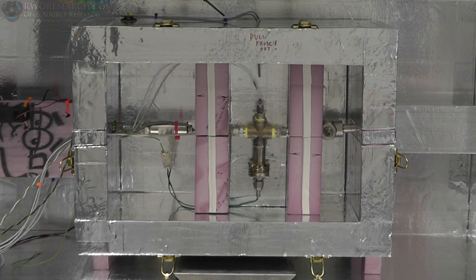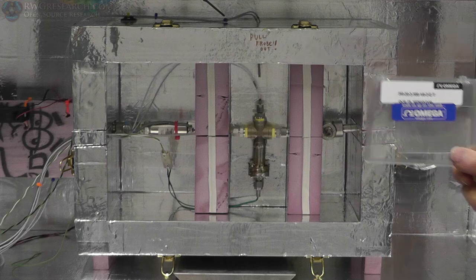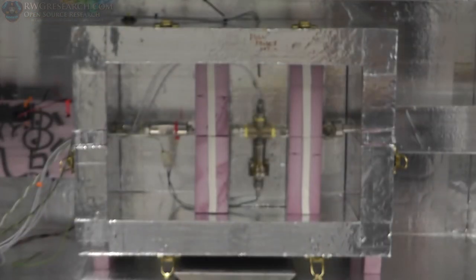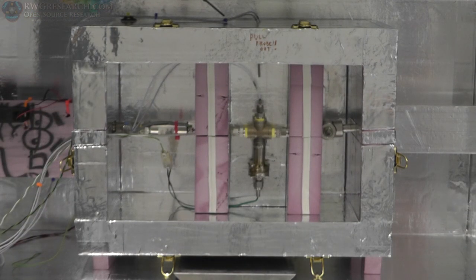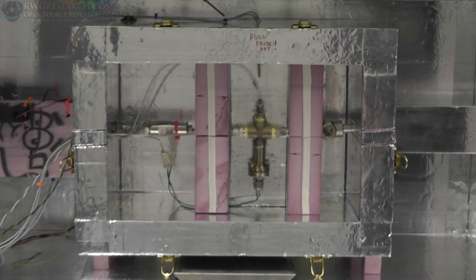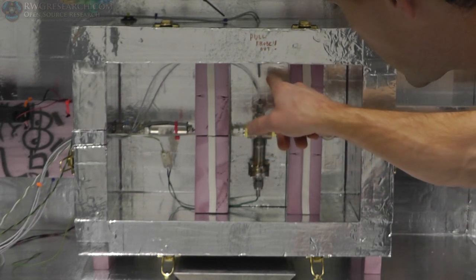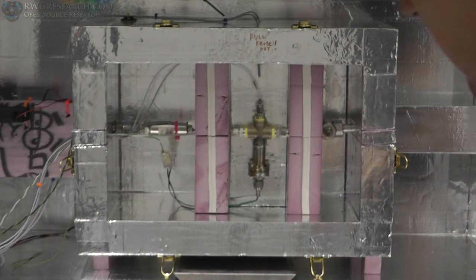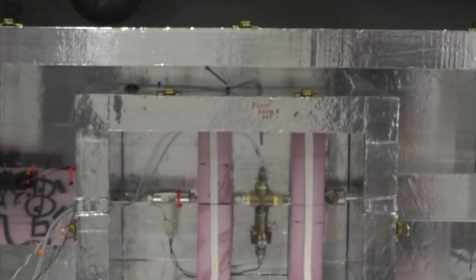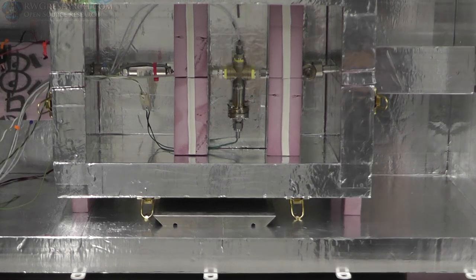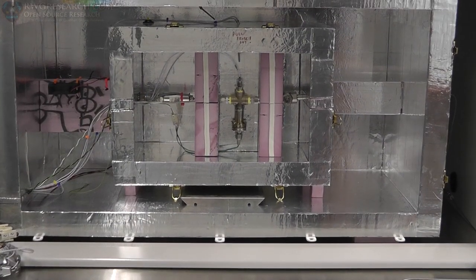Now, I've chosen four-wire RTDs because they are the most accurate that you can get. Here is the omega part number of the ones that I am using. I really like these. The four-wire allows to cancel all resistance in the wire, and only use the thermistor-type RTD at the end of the probe. So one of the probes is inside here. One is inside this chamber, which the lid gets tight against here. The back side is the same. One there, one there. And then I also have RTDs on the top, as you can see one hanging down. So there's an RTD there, and there's also one mounted to this heat plate down at the bottom. Okay, so there's one mounted on this heat plate. And that one's not really necessary, but it's been a good troubleshooting type of thing.